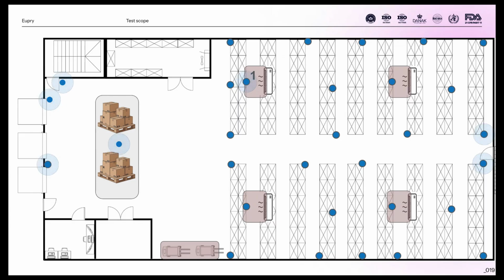In this image it's important to note that the summer and winter protocols should have fairly the same amount of loggers, or should actually be the same. We typically recommend the same logger positions during summer and winter, but there are areas you should be more concerned about in summer. When protocols show that you've done a risk assessment for each season, it shows the auditor you've thought about the risks in summer and in winter, and you'll go through the audit more easily.